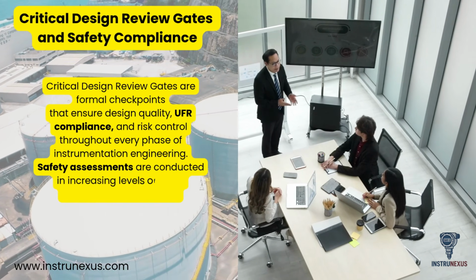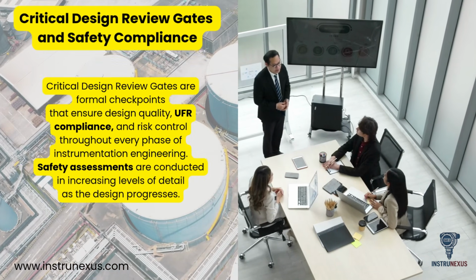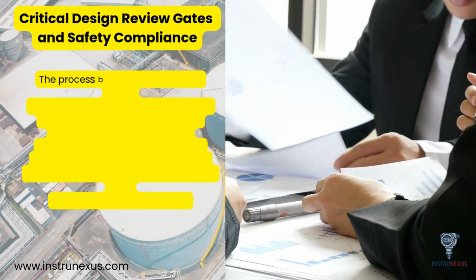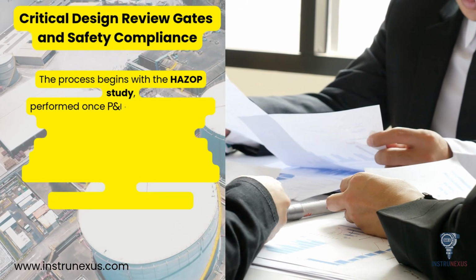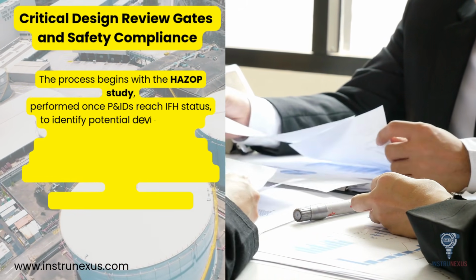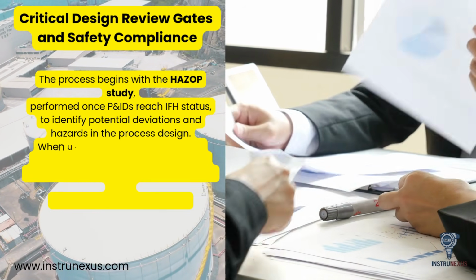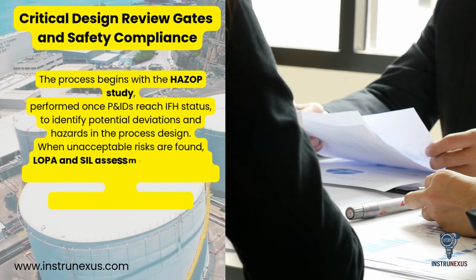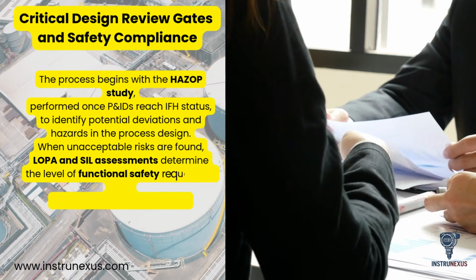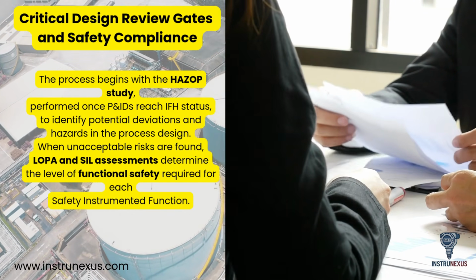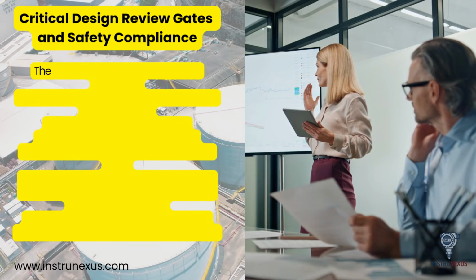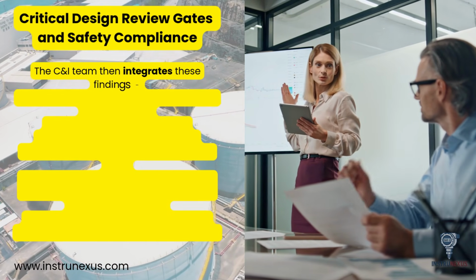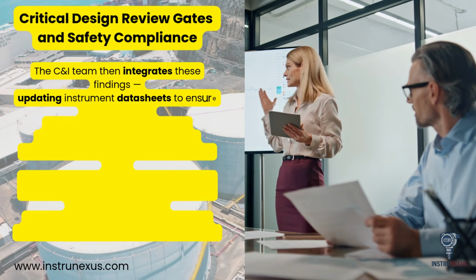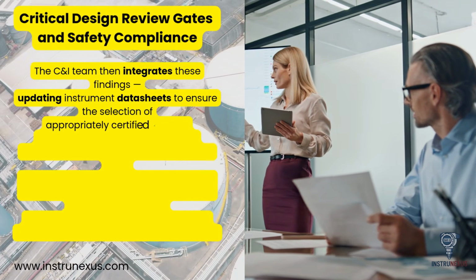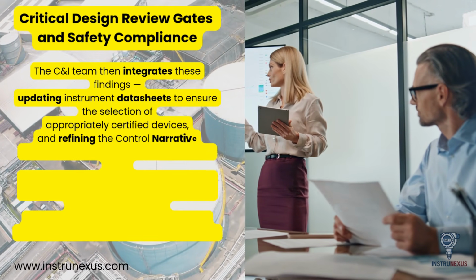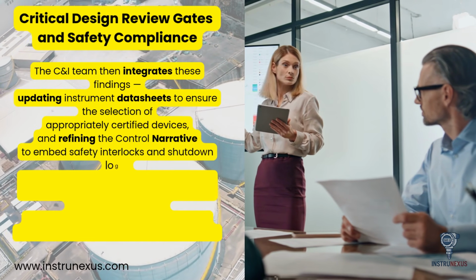Safety assessments are conducted in increasing levels of detail as the design progresses. The process begins with the HAZOP study, performed once P&IDs reach IFH status, to identify potential deviations and hazards in the process design. When unacceptable risks are found, LOPA and SIL assessments determine the level of functional safety required for each safety instrumented function. The C&I team then integrates these findings, updating instrument datasheets to ensure the selection of appropriately certified devices and refining the control narrative to embed safety interlocks and shutdown logic.